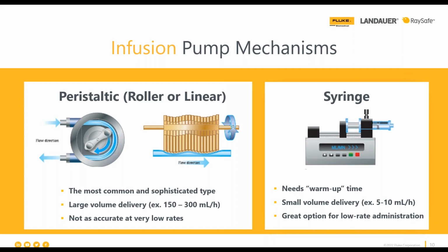So things you might see are peristaltic pumps—the roller style pump on the left, used a lot in large volume applications like feeding pumps or heart-lung bypass machines, where you're moving large volumes of fluid. But if you need finer control or smaller volumes, you might see a linear peristaltic pump with a set of fingers that push through and deliver the fluid. This is very common in a lot of infusion pumps.